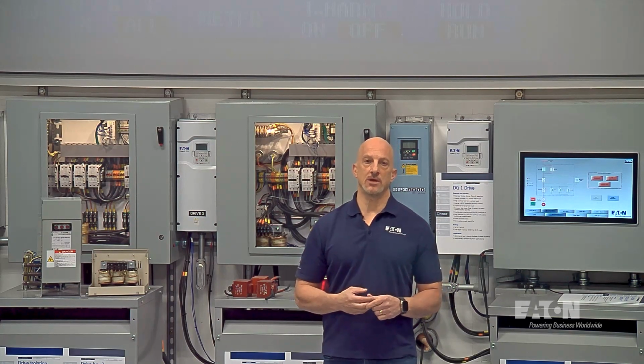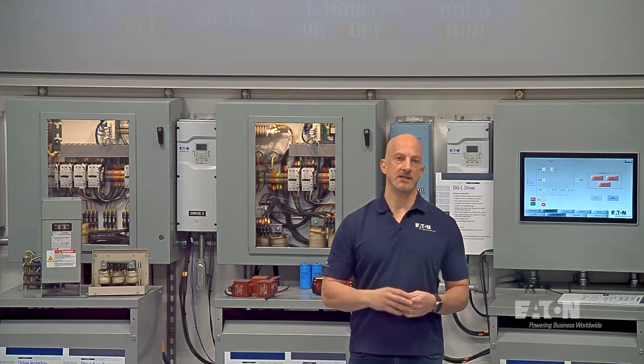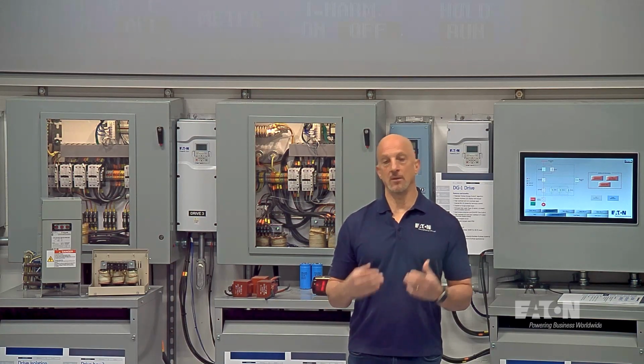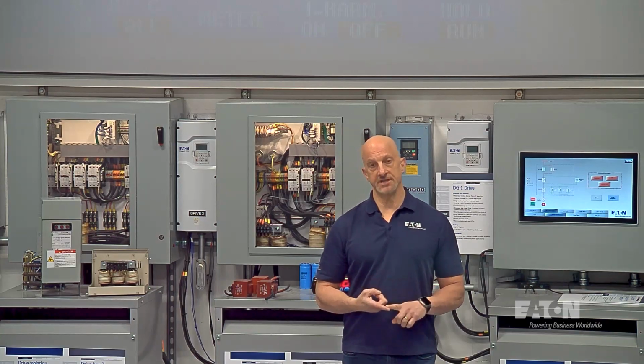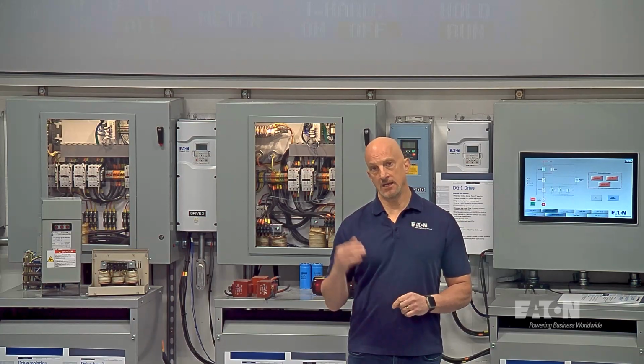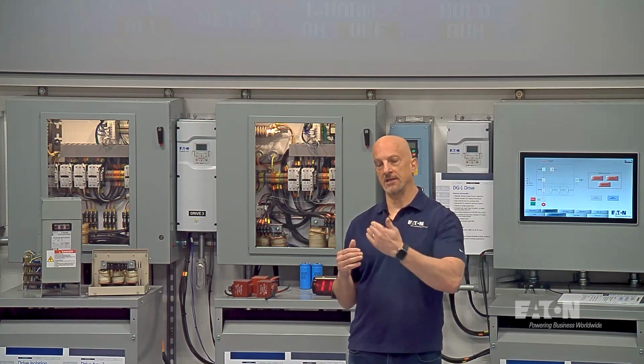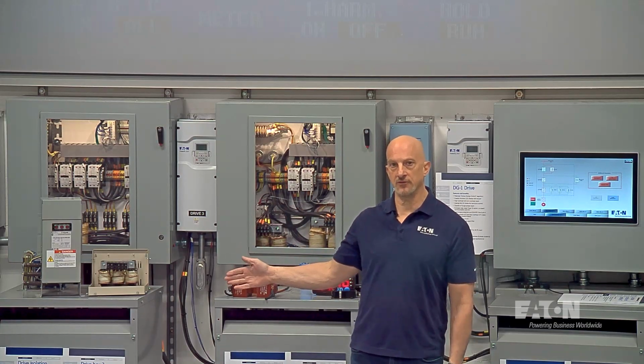So to answer the question of why I need to oversize my active harmonic filter because the harmonics that are produced by the loads are actually going to increase, let's talk about what actually is happening. So we're going to put on just a single drive and look at the harmonics coming into the system and the harmonics right at the drive.